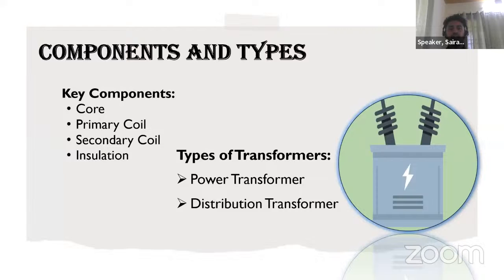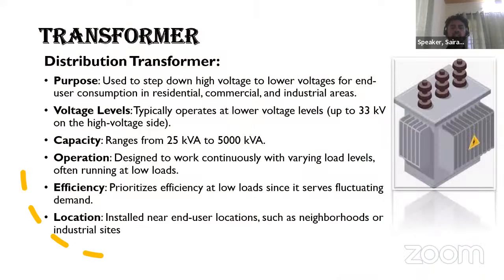The major components include the core, primary coil, secondary coil, and insulation. These are the major components of the transformer. Coming to the types of transformer, there are two major categories that we will be prioritizing: power transformers and distribution transformers. Distribution transformers are used for stepping down from higher voltage to lower voltage. These are mostly at industrial sites and residential sites, where we get the energy transferred from the grid or substation, and then directly utilize it at the user end. This purpose is served with the help of the distribution transformer.